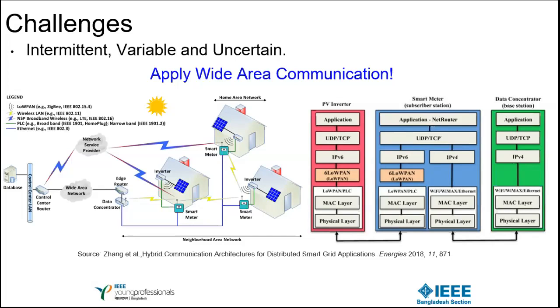So we have distributed PV generation resources. The main issue for a distribution system operator is achieving better understanding or accurate visibility of individual PV generation. Why is this important? As I said, this PV generation has reverse power flow, so it can even inject power back into the grid, which is not the traditional case.